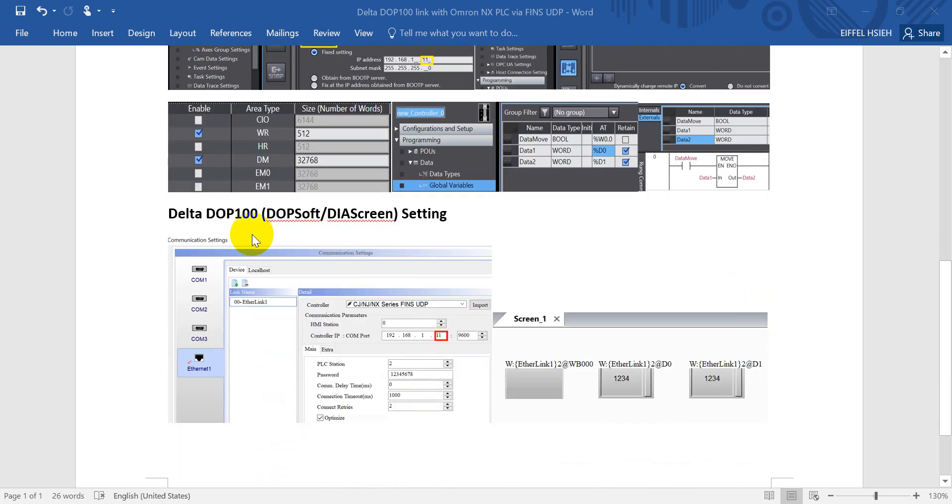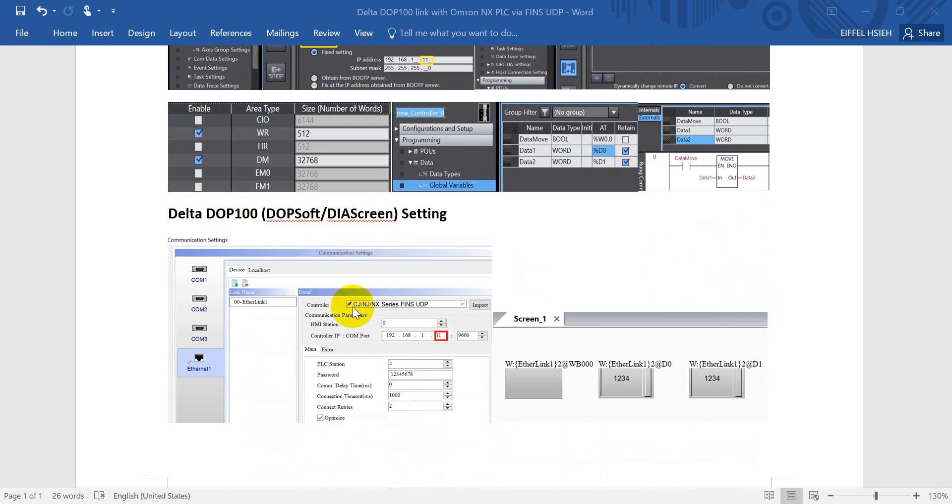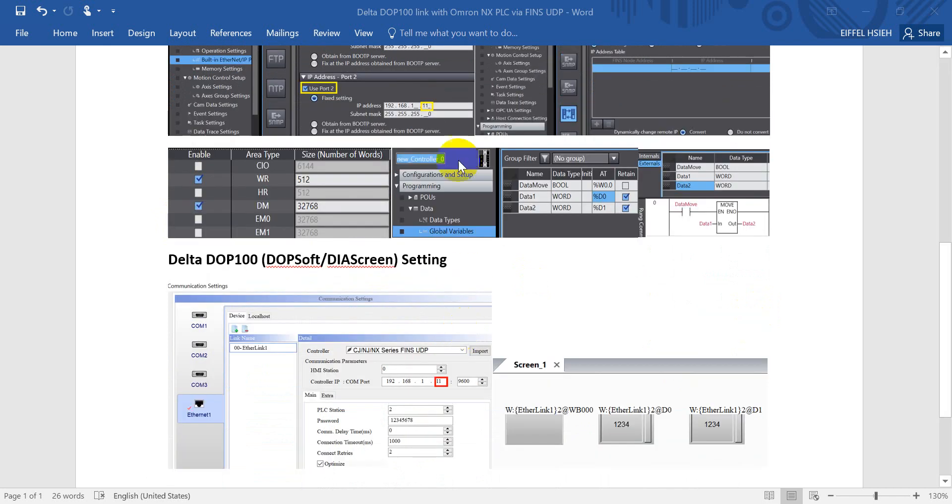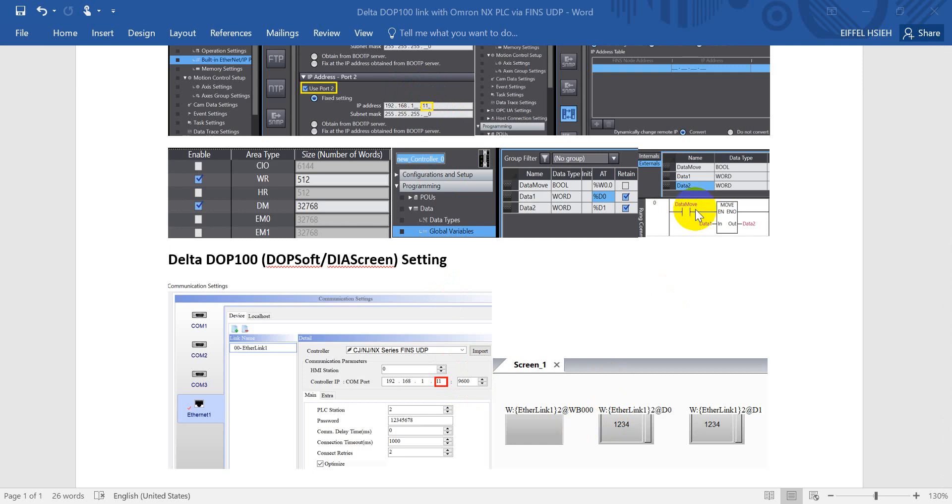After that would be Delta DOP or DIA screen setting. So here you can see we will select the NX series FINS UDP. And then this is the IP address we assigned in our previous. Then would be the port number. And based on the program we added in the Sysmac Studio, here we will add one push button.